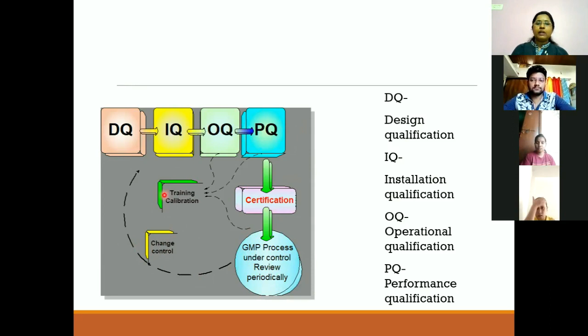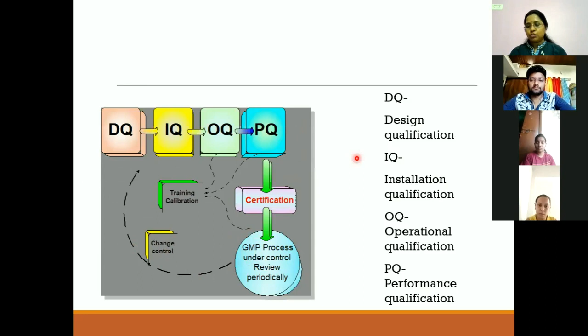And this is how they actually interlink with each other. Design qualification links with installation, that links with the operational, and then ultimately the performance. Once the performance qualification is satisfied, it gives certification that the equipment is working well, and this current GMP process is kept under control and reviewed periodically. And this again goes back to the design qualification. This continues, and if any change control is there in between, it might be possible. If there is continuous use of the equipment, change control would be there. And again the training and calibration of the same, and this again continues for the equipment for its proper working.